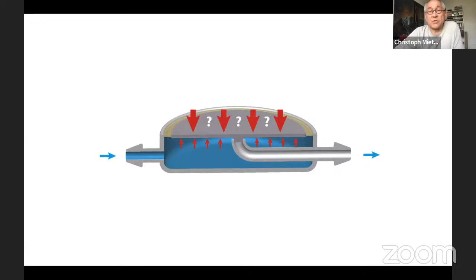Looking at the physics of this device from the side: this is the membrane, the proximal force acts on it, and the distal force tries to close the device. The closing force acts on the small area, the opening pressure acts on the large area. Using the equation that force equals area multiplied by pressure, since this area is very large, the function depends mainly on the proximal pressure, the IOP, which is ideal — we can skip the importance of the distal pressure.